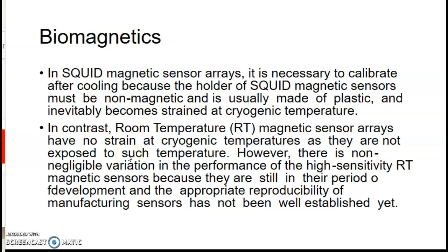So in SQUID magnetic sensor arrays, it is necessary to calibrate after cooling because the holder of SQUID magnetic sensors must be non-magnetic and is usually made of plastic, and inevitably becomes strained at cryogenic temperatures, which is what the SQUID is used to operate.